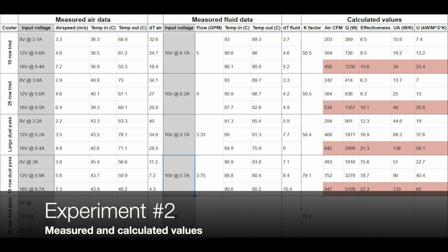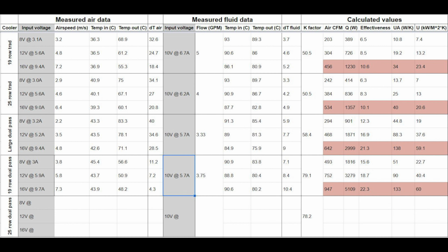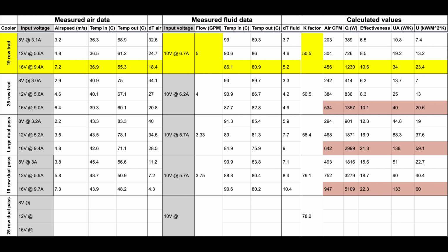Now, running all these through the same calculator, we got new values. So up on the screen now, we're looking at the secondary set of experimental data. Once again, the 19-row traditional, at the highest value of fan speed, it pulled the best values. So we were looking at almost the exact same U and UA values. First experiment showed 24 for the U and a 35 for the UA. So that shows us almost dead on they were the same.